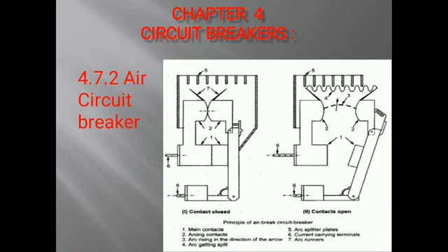For systems having low inductance, arc gets extinguished before reaching extremity of runners, because lengthening of arc will increase the voltage drop, which is insufficient to maintain the arc.